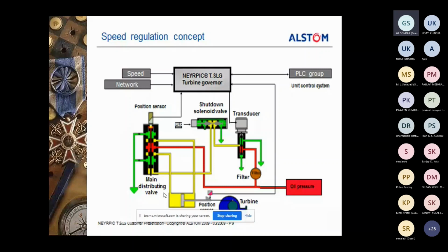There are RSD, meaning rapid shutdown 1, rapid shutdown 2, and ESD. Rapid shutdown 1: all mechanical faults are treated as RSD 1. All electrical faults are RSD 2. Emergency is ESD. There is an emergency ESD button in front of the operator in the panel itself.